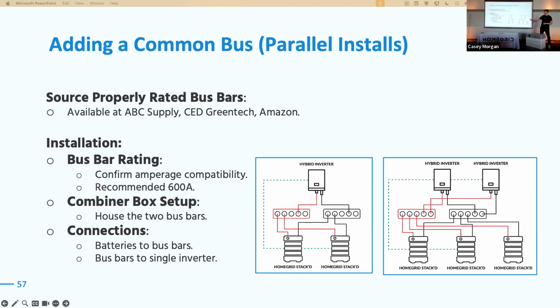One thing to note is those common bus bars need to be rated correctly for the amperage passing through. For example, with Sol-Ark 15Ks, each can charge and discharge at 300 amps. So with 2 of them, you'd need 600 amp rated bus bars on each side. Green Tech carries bus bars, and I also recommend a brand called Blue Sea Systems, based here in Florida, which sells good options for these.